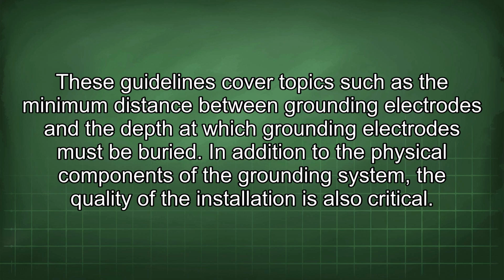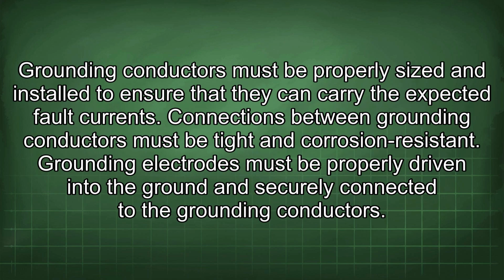In addition to the physical components of the grounding system, the quality of the installation is also critical. Grounding conductors must be properly sized and installed to ensure that they can carry the expected fault currents. Connections between grounding conductors must be tight and corrosion resistant. Grounding electrodes must be properly driven into the ground and securely connected to the grounding conductors.